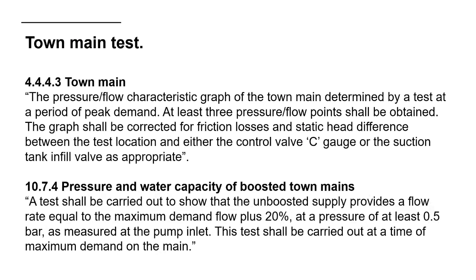It doesn't tell you how to determine peak demand, but what's fairly typical is that you would repeat the test several times during a day. So do one in the morning, one in the afternoon, one at night, and then repeat that on several days, and you can figure it out yourself. Take basically the worst case scenario from any of those tests. You're looking at pressure and flow that is taken from the town main.